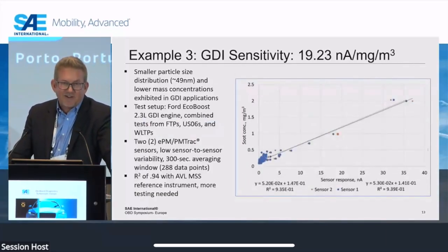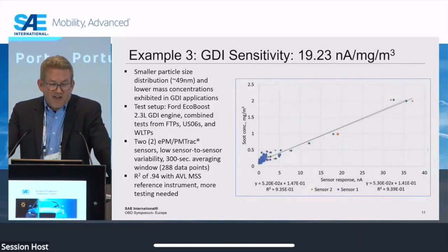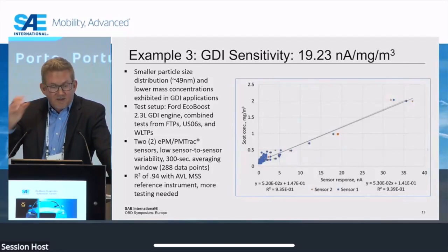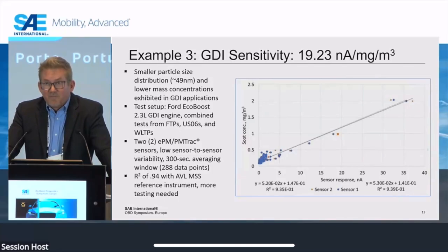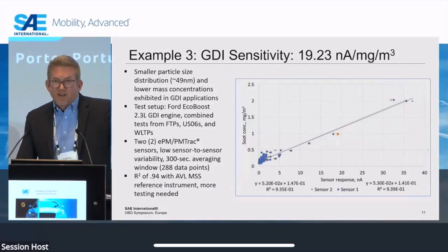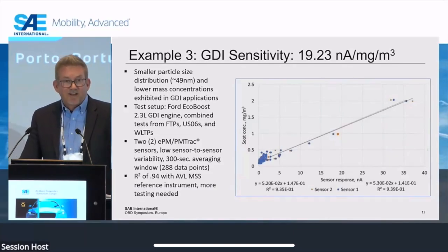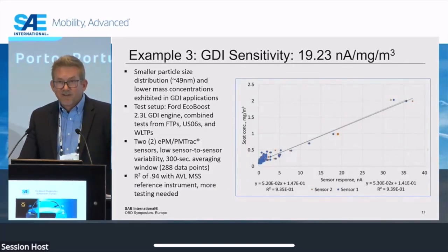Example number 3 is actually gasoline direct injected. So this is a GDI engine, a 2.3 liter EcoBoost, and significantly higher sensitivity, right? So 19.2 nanoamps per milligram per cubic meter. You also start to see, and this is a 49 nanometer mean size distribution, smaller particles, like higher number, smaller particles, as one would expect from GDI.